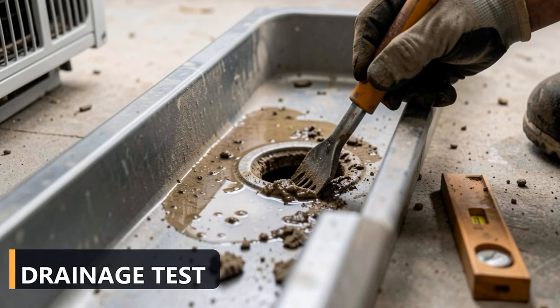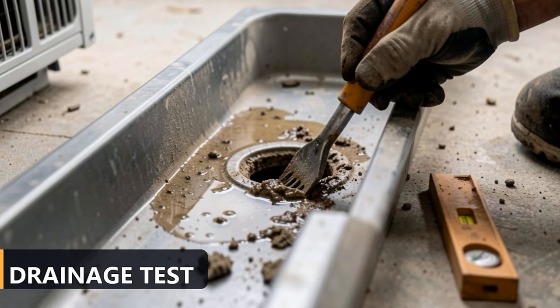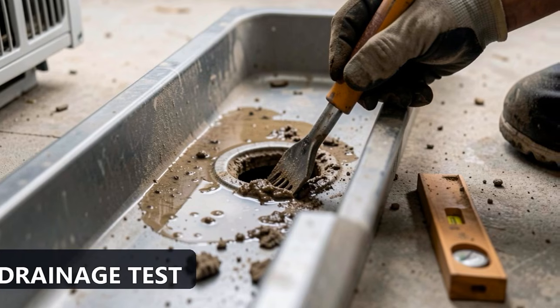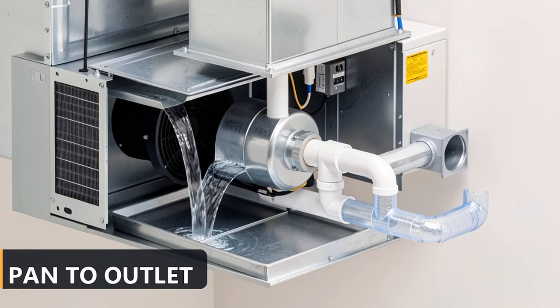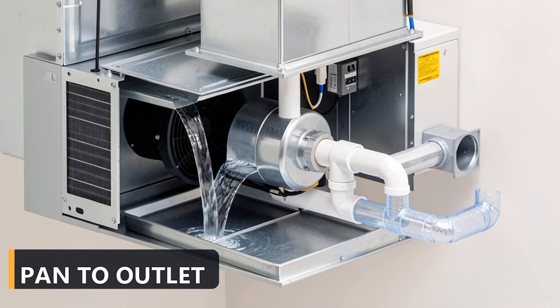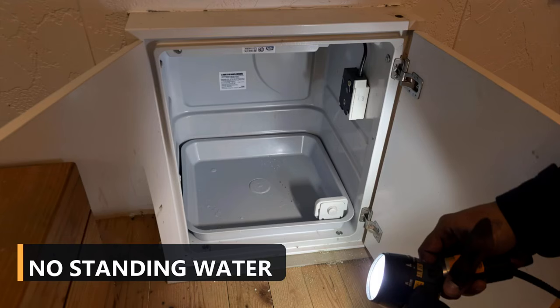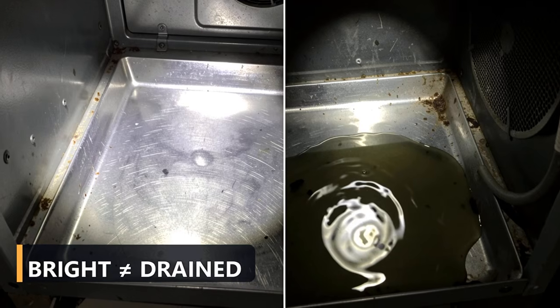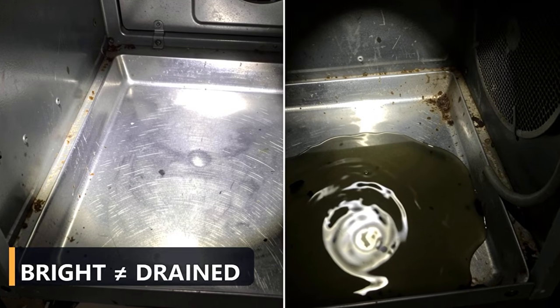After loose material is physically removed using the method approved for the unit, clean water should travel freely from the pan to the exterior discharge. There should be no standing water, no leak around the cabinet, and no float switch shutdown. If water remains after the bright surface is dried, the visible cleaning result was only cosmetic.